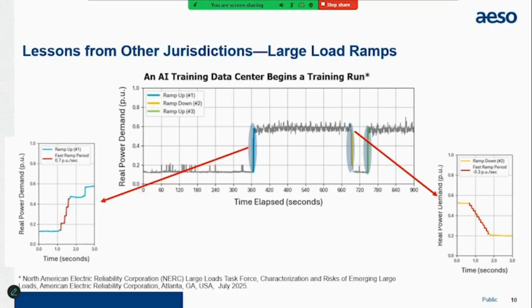As I mentioned, one of the load characteristics of data centers is large load ramps. This picture shows the load profile for a real AI training data center, and we can see that within a fraction of a second, the data center ramps up and down more than 50% of its capacity. Now imagine a hyperscale facility with 500 megawatts or 1,000 megawatts. If we were to have such a step change in the load, what could happen to the balancing and stability of the system? Because this type of ramping is like a step change in the system.